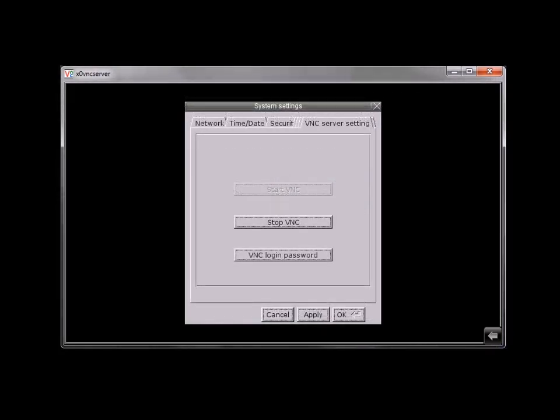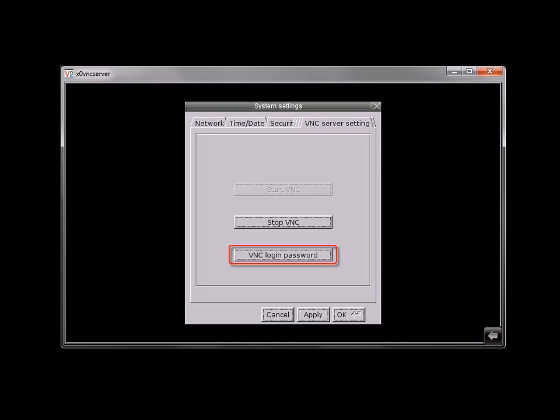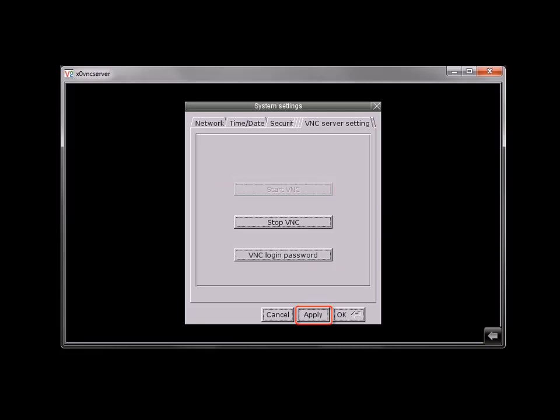Select the second to last tab on the right, the VNC server tab. This tab can be hard to see—it appears as a tiny sliver beneath the firmware tab. Click VNC login password to set the password used to log in to the HMI from the VNC application. Select Start VNC and then click Apply and OK.